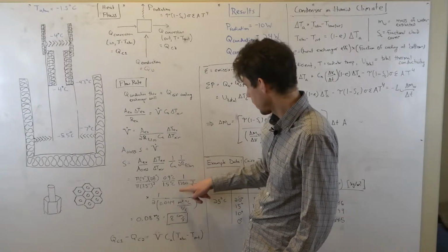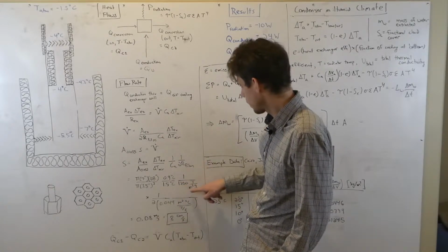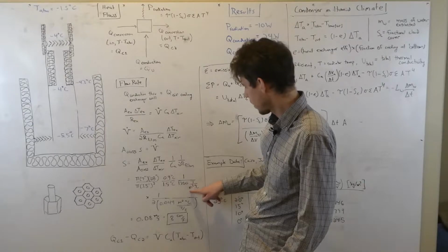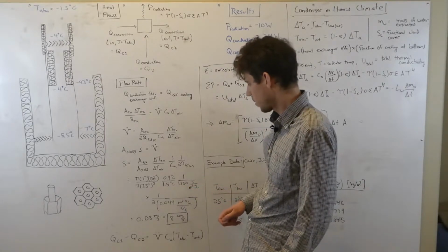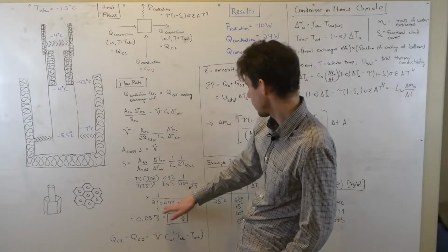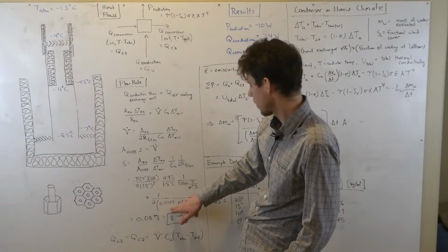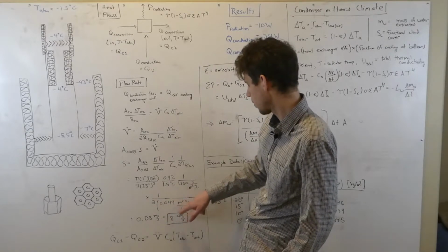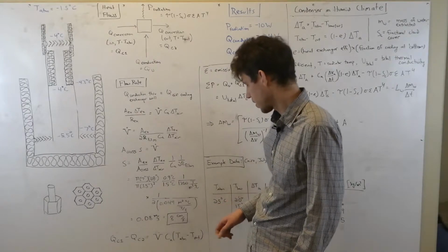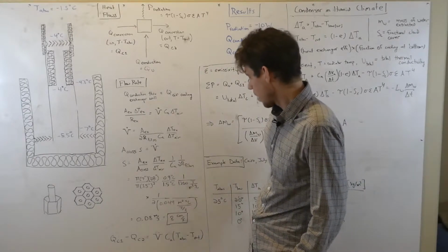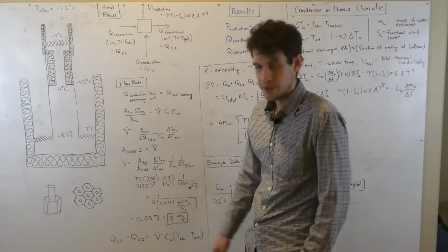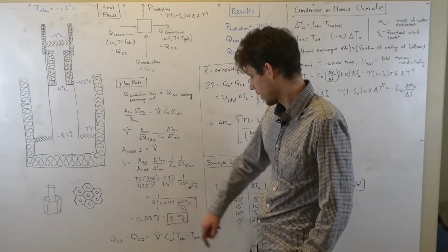Then 1 over the volumetric heat capacity of air, which is 1300 joules per meter cubed per degree Celsius, and then 1 over 2 times the R value of an air film, which is 0.044 meters squared degree Celsius over joules per second. Solving, you get 8 centimeters per second, or 0.08 meters per second.